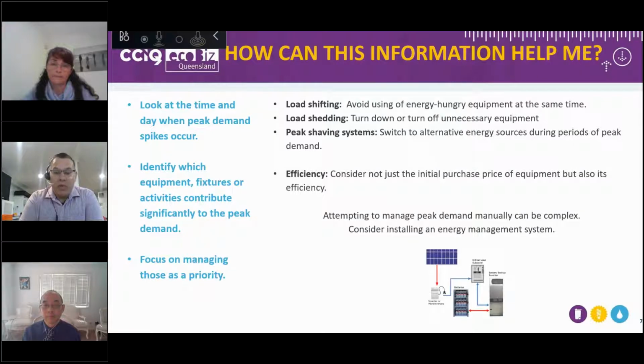So what in fact happens here is that you could have a period in the day or in your operating method where your peak demand is really high, and that's what you'll actually get charged for the whole month. This is why it's important to be aware of what your load curve looks like, so that if you do have any particular outlying periods of time, you can address those. And how do you address them? Well, we can address them in the following ways.